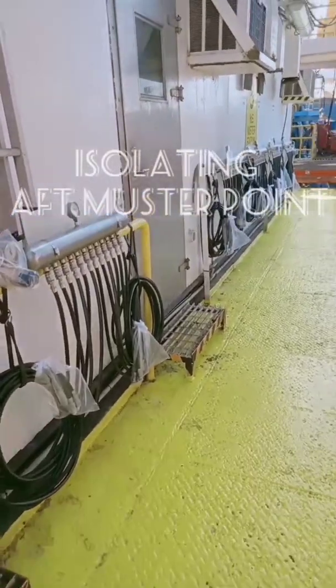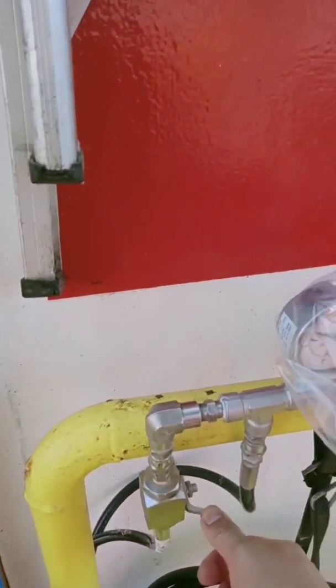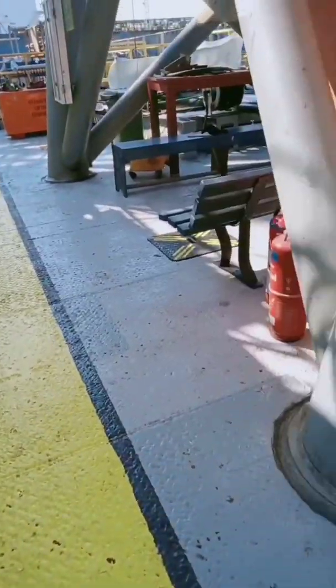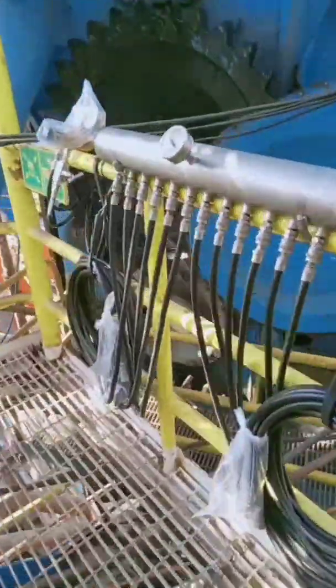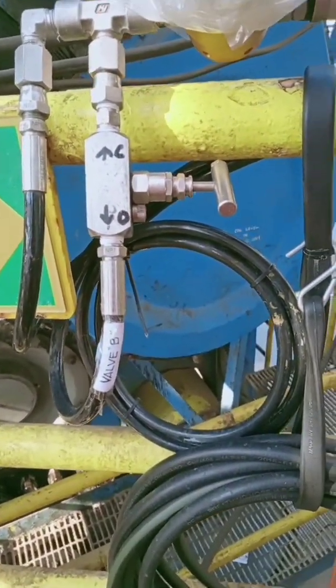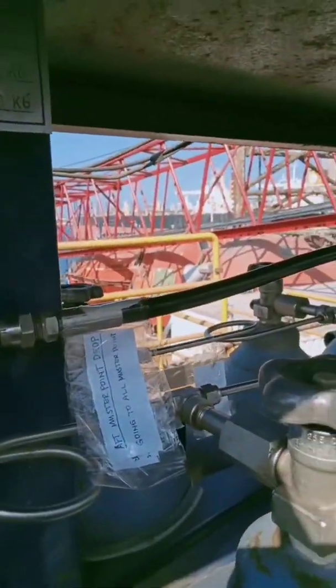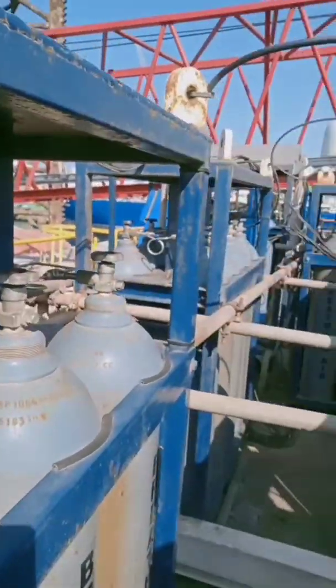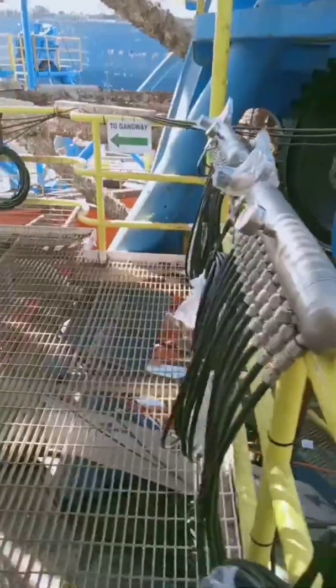This is how you isolate all the muster points. For the aft muster point, you need to close valve A, and close valve B located at the starboard muster point. Also close the valve on the top deck on the cascade. Close the air supply drop, and bleed it off at the aft muster point refilling station.